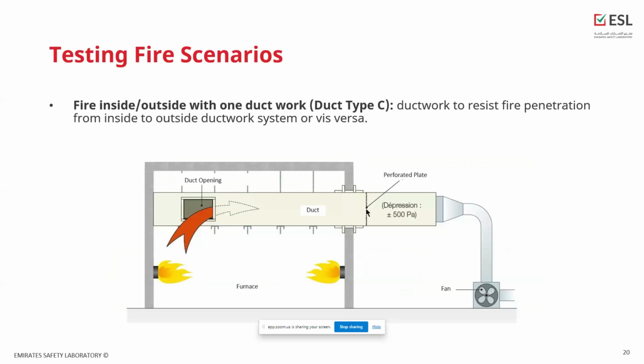For the EN standard, they introduce a new concept, if we may say that. It is because the smoke control duct, originally, needs to work under two fire scenarios. So one duct itself may come under the scenario of duct type A or duct type B. And to check and verify this point, there is a test or type of duct which is called duct type C. In this scenario, they are trying to prove that the duct will work and can perform under the two fire scenarios, fire from outside and fire from inside.